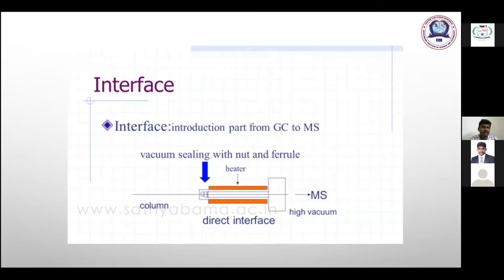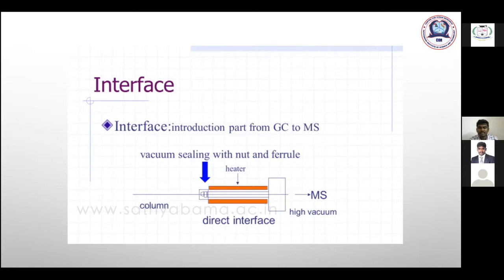The interface is a rod-like structure connecting GC with MS, sealed with vacuum. The interface temperature is very important — it is based on the final column temperature, and the interface temperature must be maintained accordingly to prevent condensation of eluted compounds.